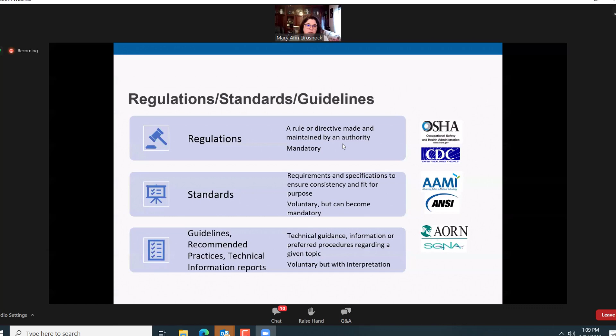Below that, then, we have guidelines such as those from professional societies, recommended practices, AAMI documents such as technical information reports, which are also called TIRs. These are also considered voluntary. But again, think about what you're claiming compliance to, and then you are expected to follow that guideline. And those are usually more specific information on a certain topic, like TIR 99, which will be related to probes and dilators processing, and very specific within endoscopes. It might be SGNA for GI scopes. So we see a narrower focus, whereas our standards really are all for, as far as ST91 goes, all types of flexible scopes in all settings. So we have a much larger fit for that guideline.